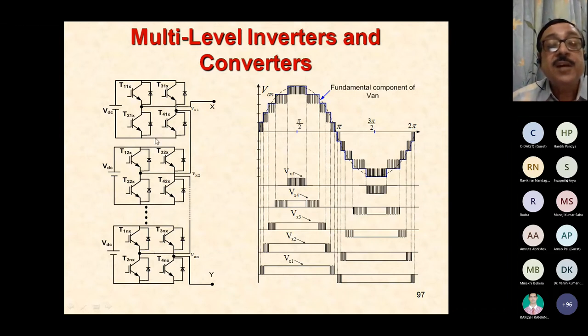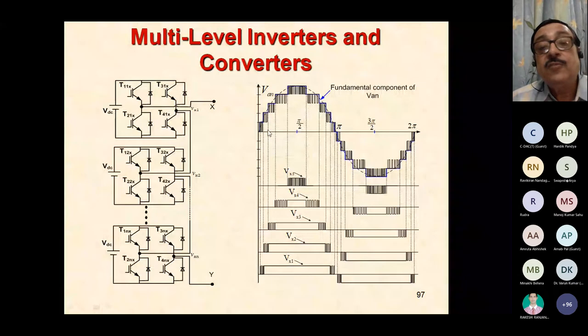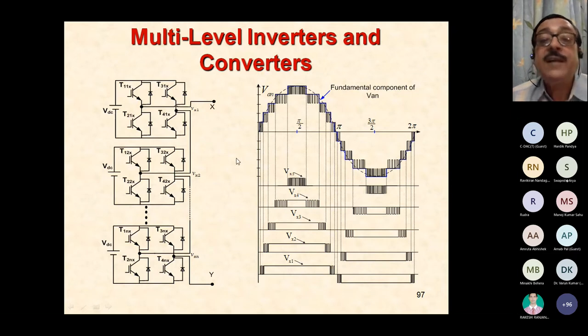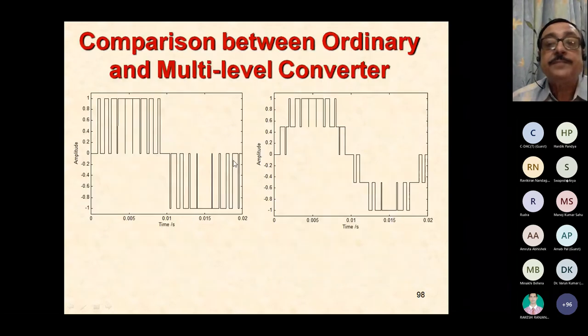Each converter structure operates with an individual cell voltage, but the outputs are all connected in series to achieve a high voltage at the output. So you can see the total voltage that is created comprises smaller steps contributed by the individual inverters, and each step comprises these DC bus voltages. So each individual device is rated at lower voltage, but the composite waveform is a higher voltage here. So this is one technique to connect the devices having lower bus voltage to a higher grid voltage.